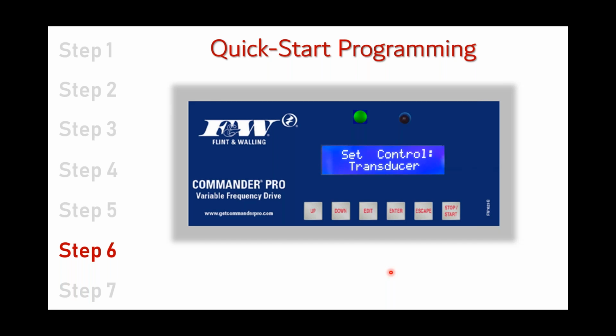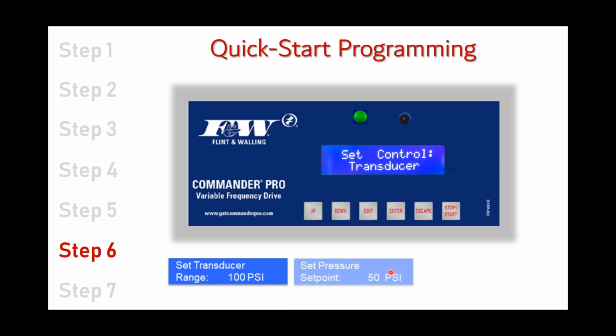Such as number 1, it's going to say, well, what's the range of the pressure transducer that you've got on this system? Well, I'll answer that. It's 100 psi. That's what we ship out with the packages. That's what we ship out with the drives, and that's a standard transducer I think the industry uses. We also have larger pressure range transducers. We go up to 300 psi, I think, but that's the exception to the rule. 95 or more percent of these that go out, more than that, 98% of them are going to go out with a 100-pound transducer. So all you do is you look at that, it's 100 pounds is already in there. You go, yep, that's what it is. You hit your enter button.